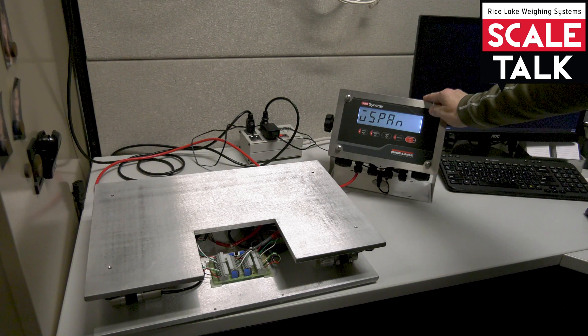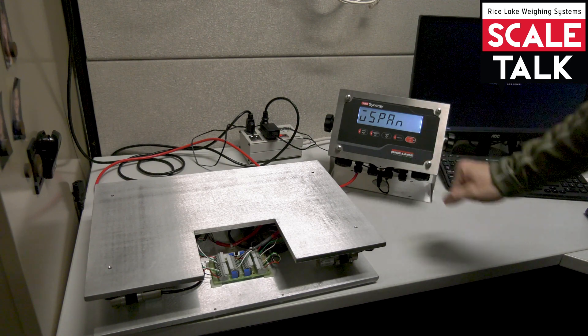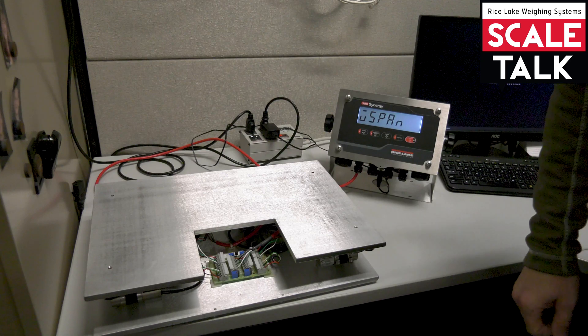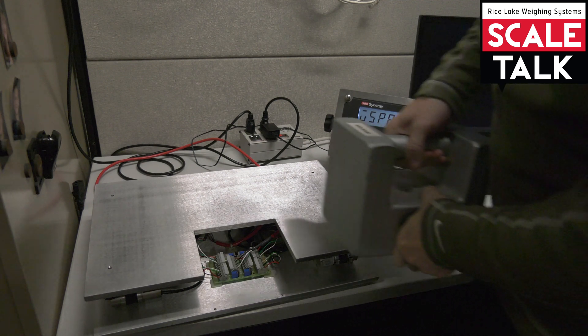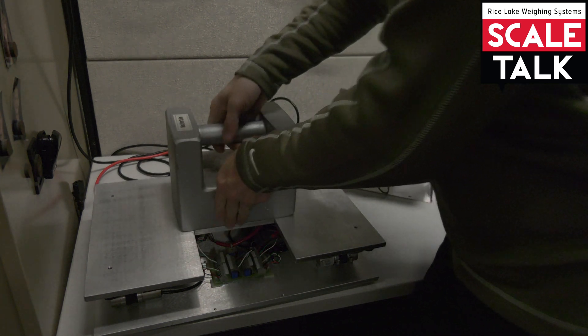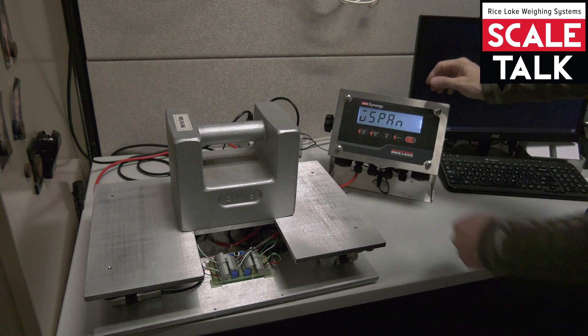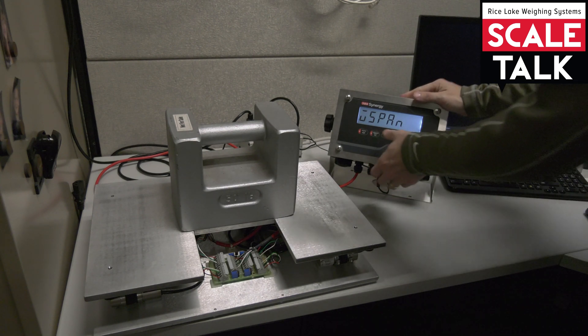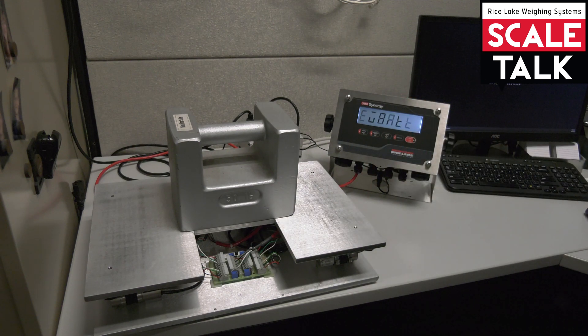So the indicator is now looking for 50 pounds to be on the scale when we execute the span. So let's go ahead and put a 50 pound test weight on the scale. Once that's in place and settled, I'm going to go ahead and press my down arrow. Execute that span calibration.